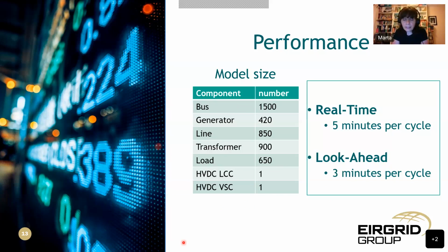With this model and the hardware implementation that we have in both sites, we have a real-time performance of 5 minutes per cycle. Most of the time, it's completed well below that. The average is about 3.5 minutes per cycle. For look ahead, we have a maximum performance requirement of 3 minutes. Again, we normally exceed that performance, and we complete the computations in about 2.5 minutes.